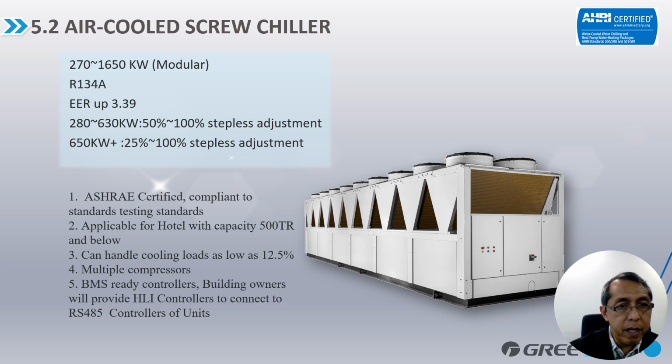It's ASHRAE certified, compliant to standard testing standards, applicable for hotels with capacity of 500 TR and below. It can handle cooling load as low as 12.5%. It has multiple compressors and it is a BMS-ready controller. Building owners will need to provide a high-level interface controller to connect to the RS-485 controllers of the units.